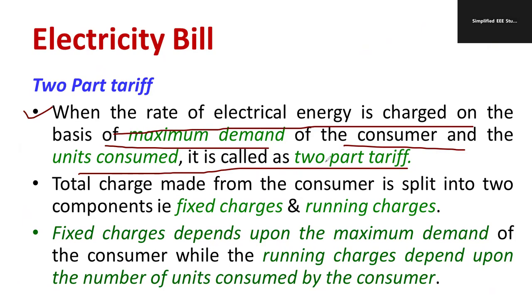The fixed charge is one component that directly depends on the maximum demand, and the energy consumed is considered as the running charge. Fixed charge will be directly depending on KW, that is maximum demand, and the running charge will be directly depending on KWh, kilowatt hour. One is power and the other one is energy.